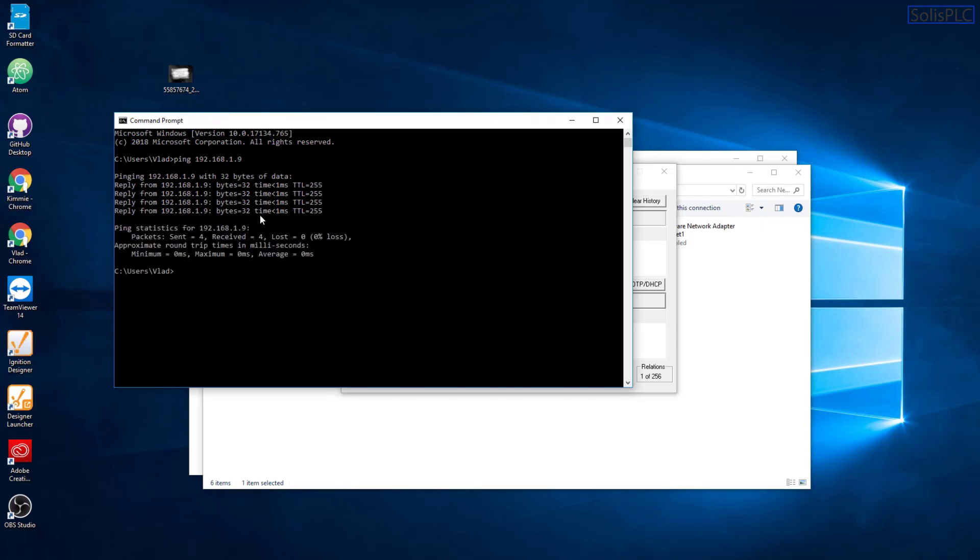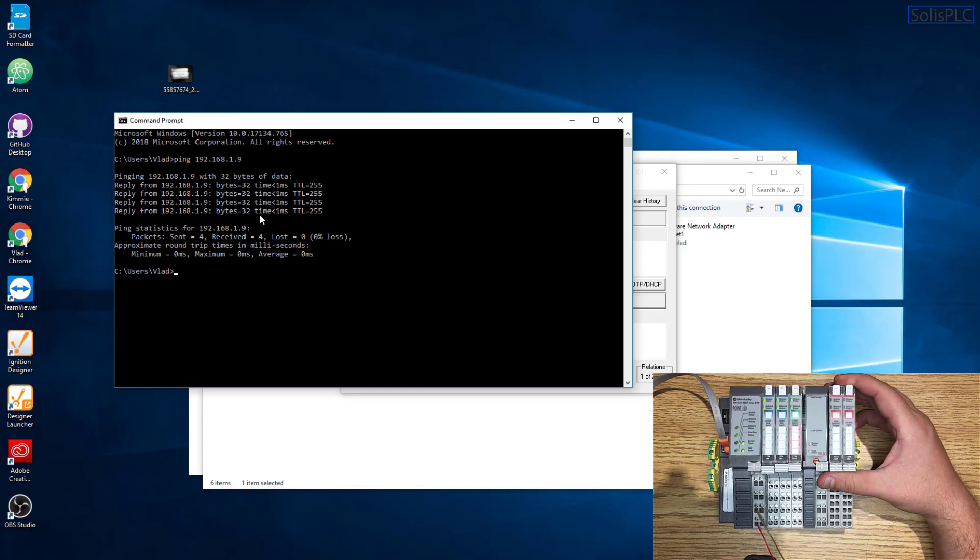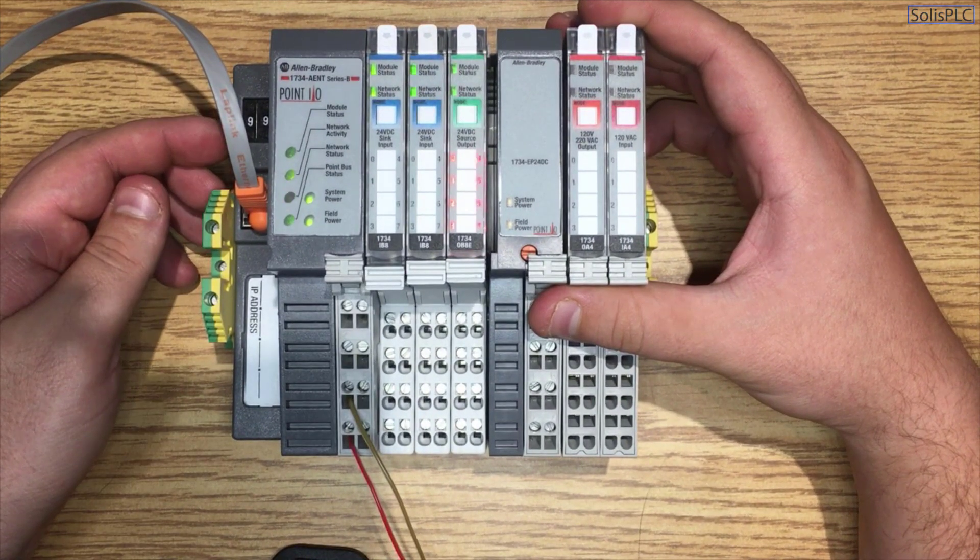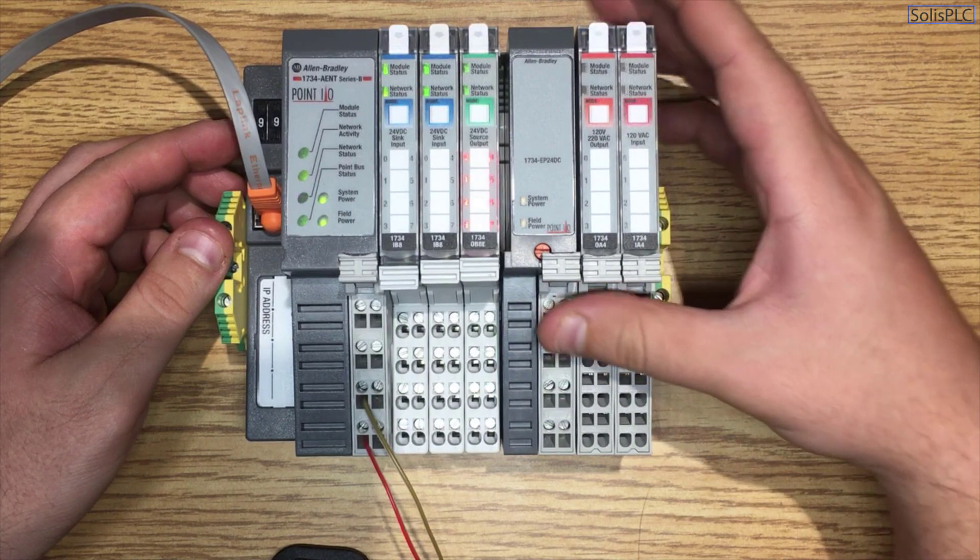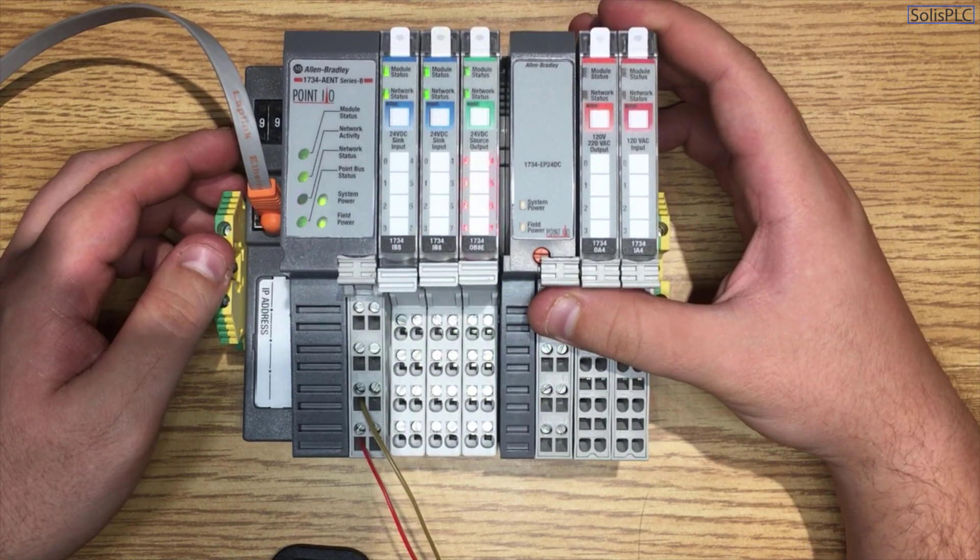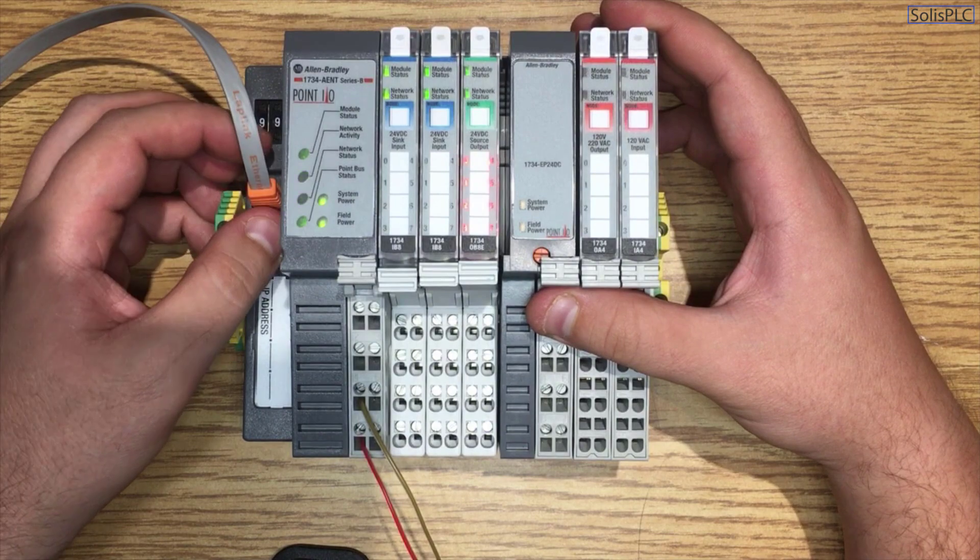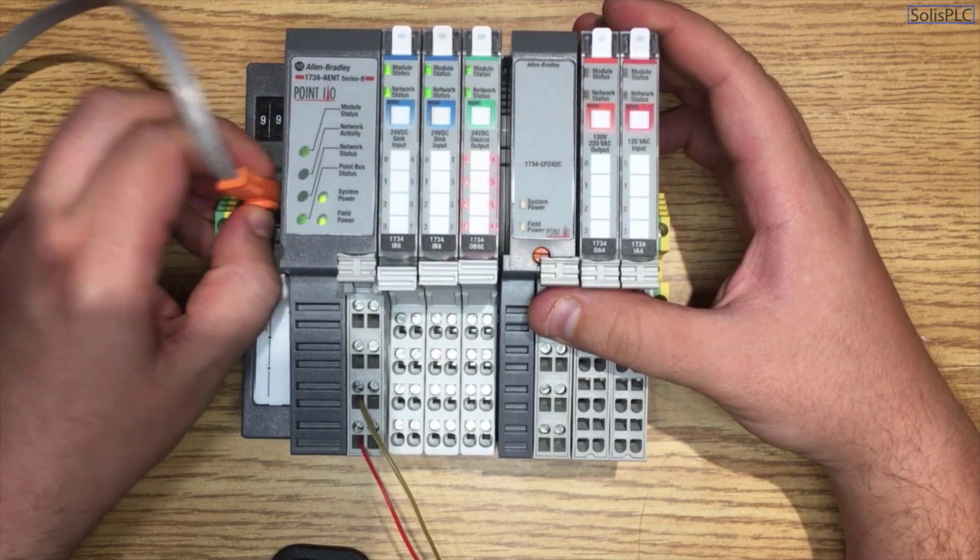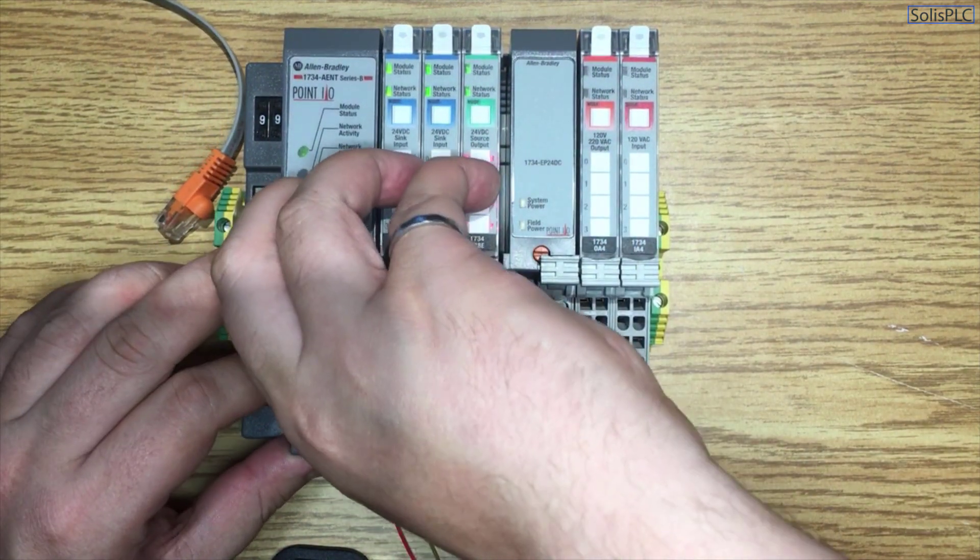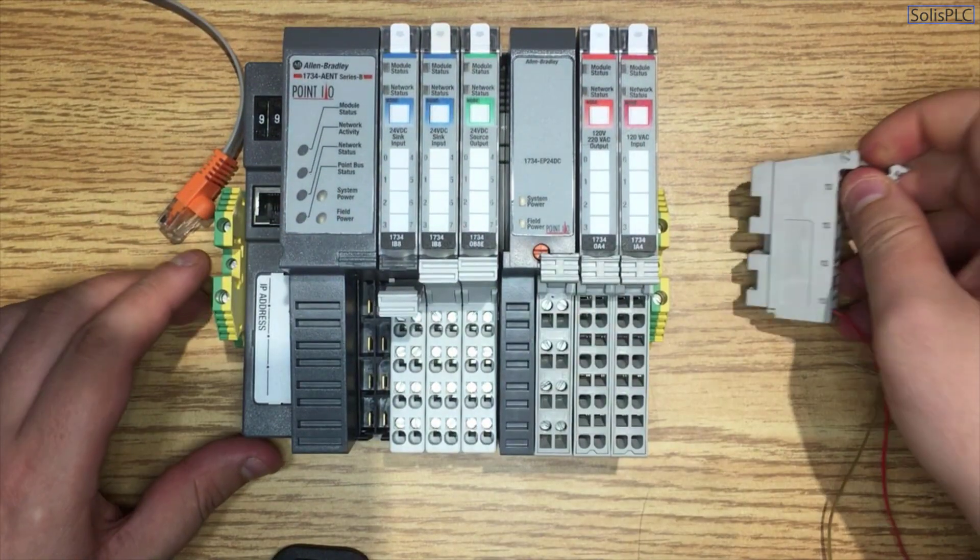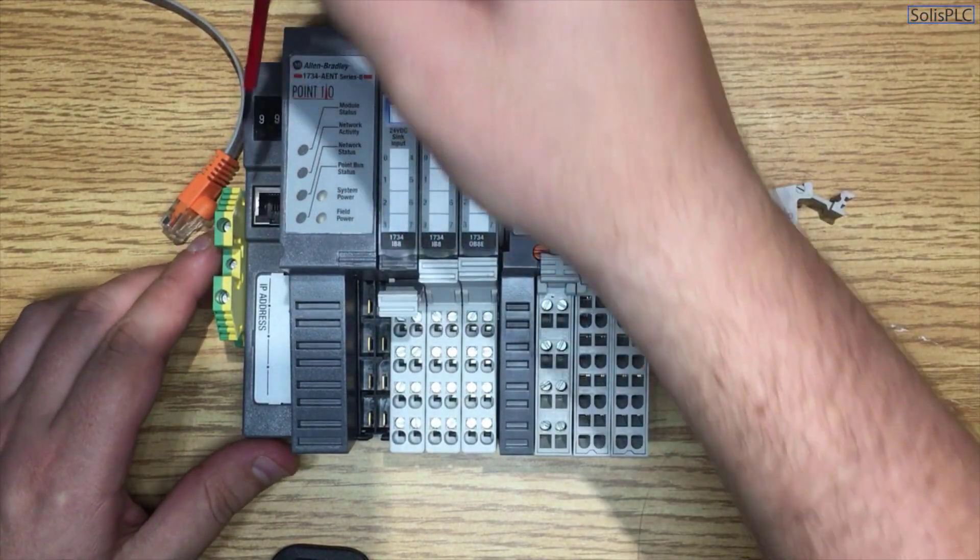Now, that's the way to set the IP address if it's not going to be on the private network, even though we gave it a private network IP address. Now, the other thing that I want to demonstrate is that this thumb wheel gives you the flexibility to set the IP address without having to go into the settings if the IP address is on a private network. So I'm going to, first of all, unplug this cable. I'm also going to power down the module. You do want to power down prior to making changes or after you finish making them.